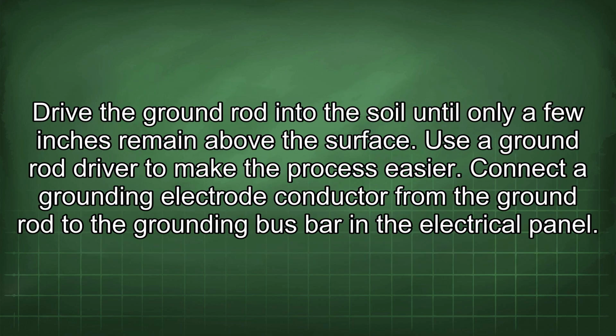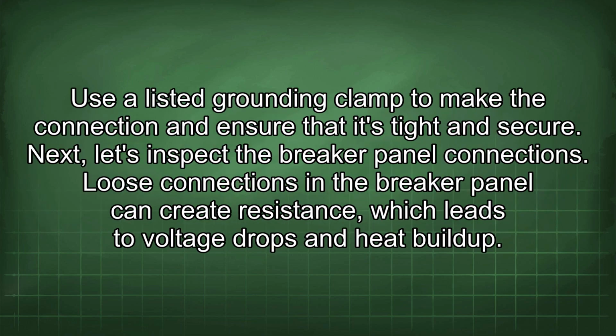Drive the ground rod into the soil until only a few inches remain above the surface. Use a ground rod driver to make the process easier. Connect a grounding electrode conductor from the ground rod to the grounding bus bar in the electrical panel. Use a listed grounding clamp to make the connection and ensure that it's tight and secure.